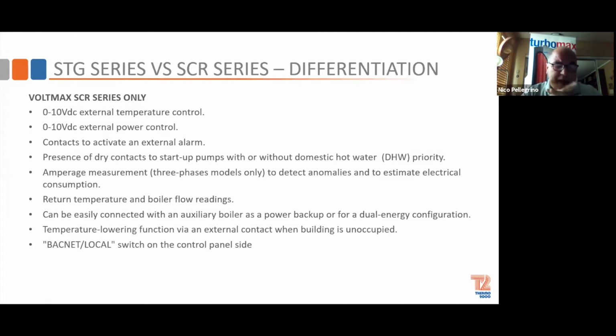It's BACnet compatible. It's not wireless. Contacts are also available for external alarms. You can set up the controller to send emails with the alarms. You have pump relays available. The amperage measurement is only on the 3-phase models. And you have return and boiler flow readings on the controller. I'll go through that right now.